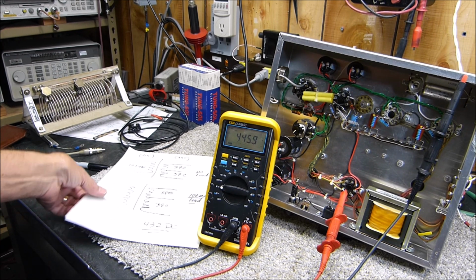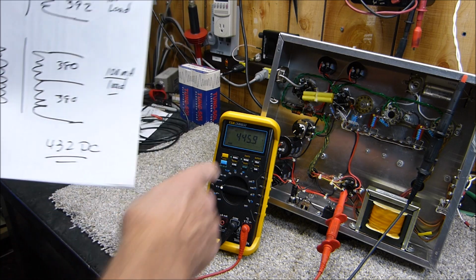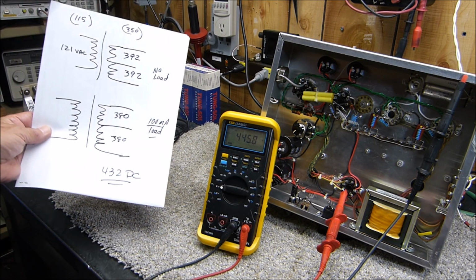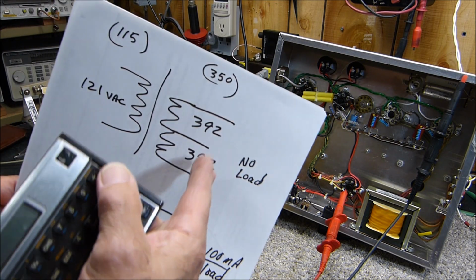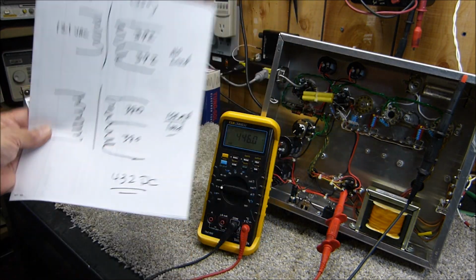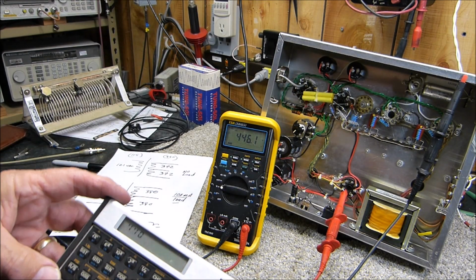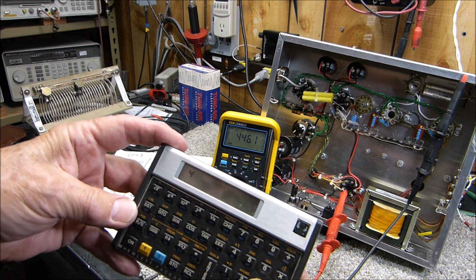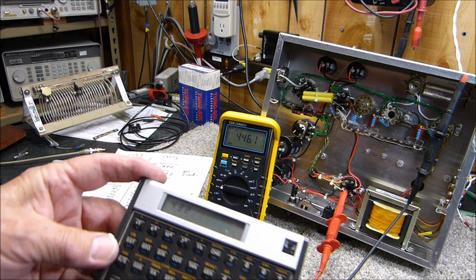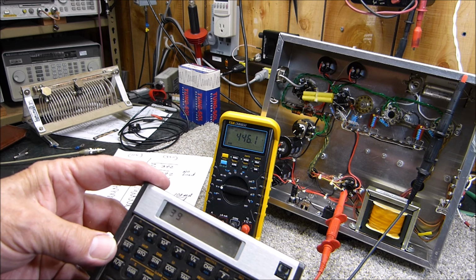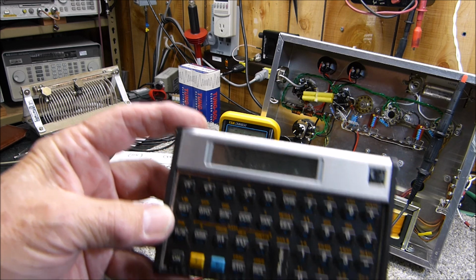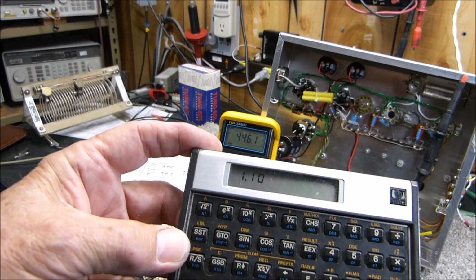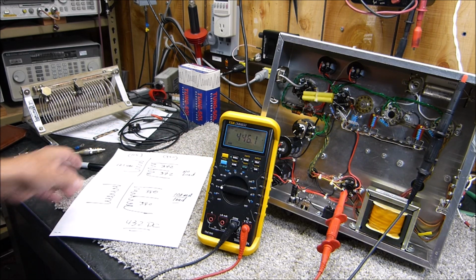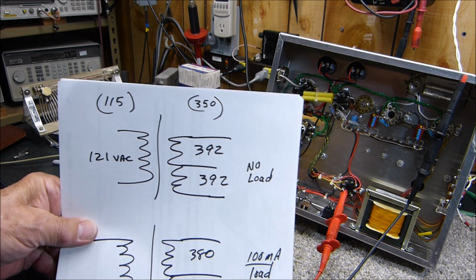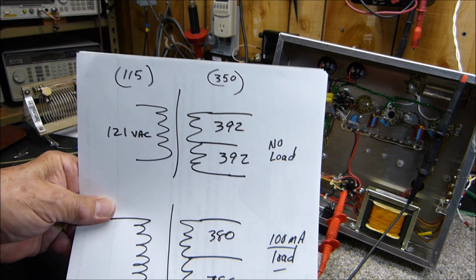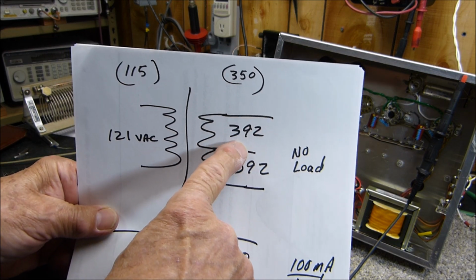If you actually go to the DC, the 445, let's use that one. From the 392 open circuit to the DC, what would that be? 432, divided by 392, that's 110%, 1.1. So if you want the shortest shortcut, you could measure your open circuit voltage.